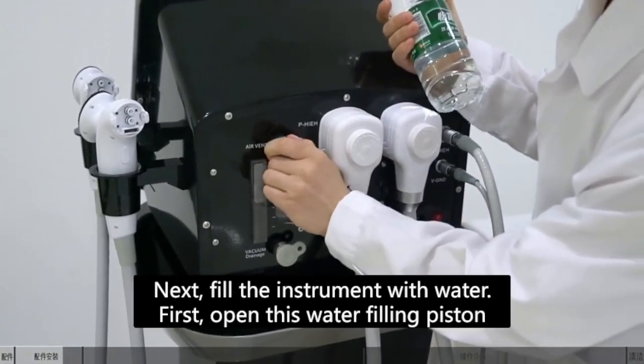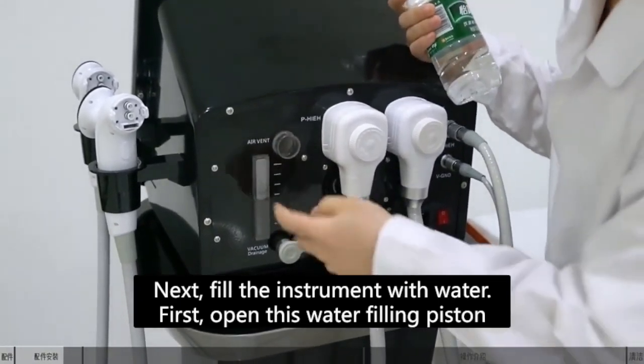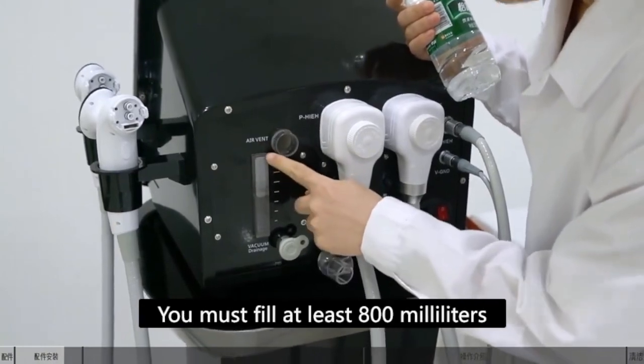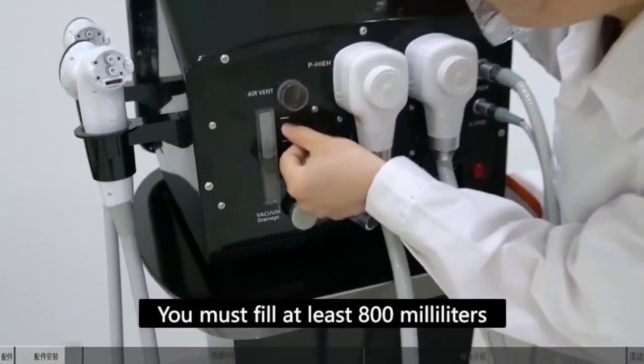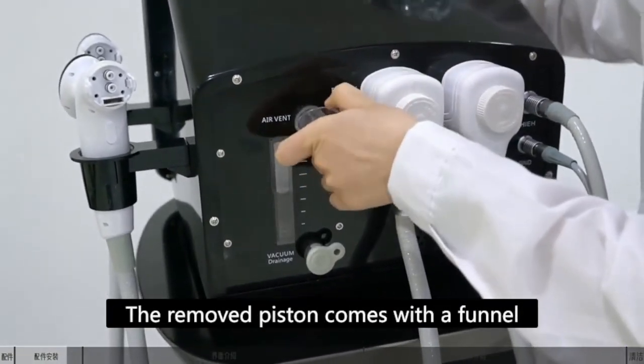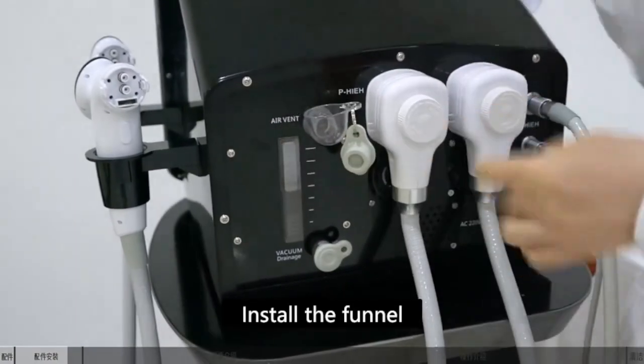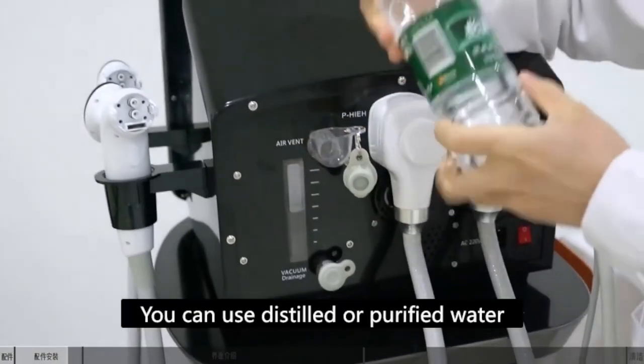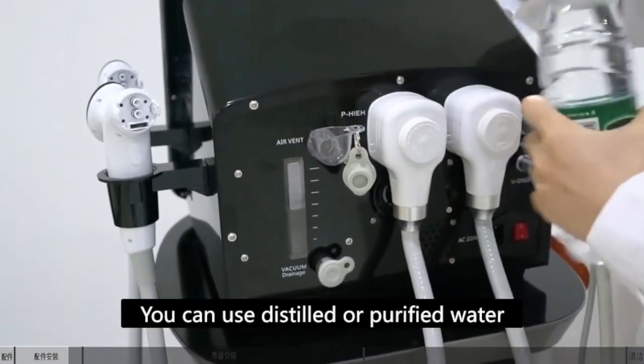First, open this water-filling piston. Before powering on the instrument, you must fill at least 800 milliliters. That is up to the second graduation mark. The instrument can only be powered on after filling. The removed piston comes with a funnel. Install the funnel. You can use distilled or purified water.